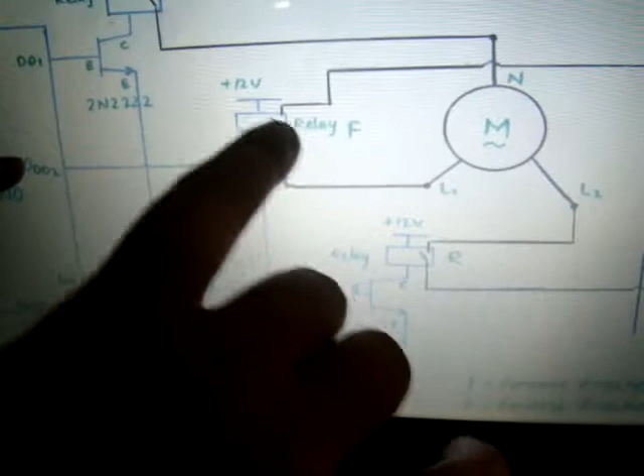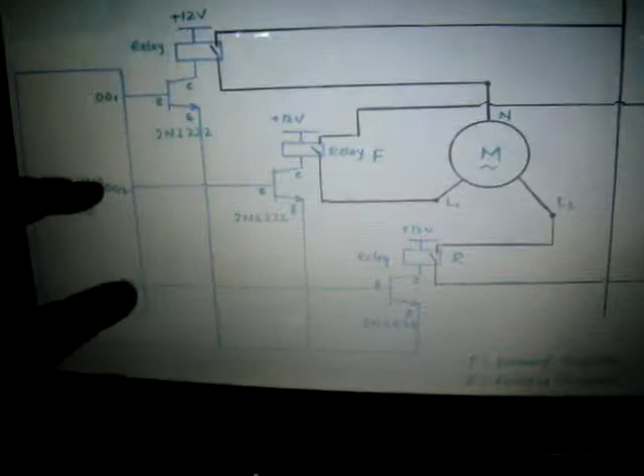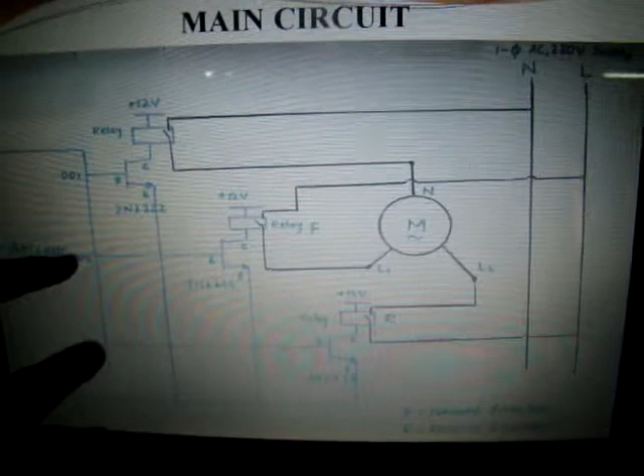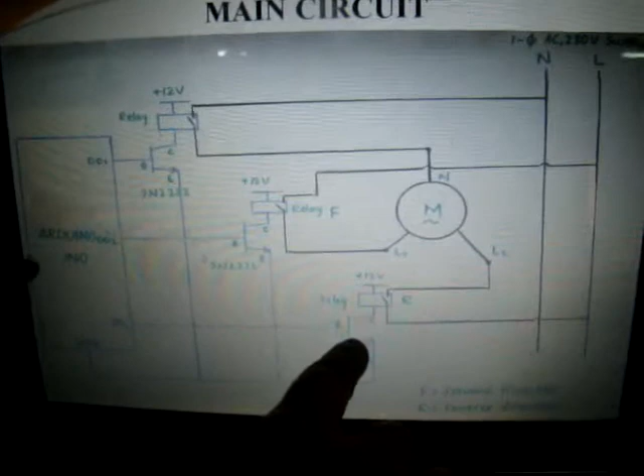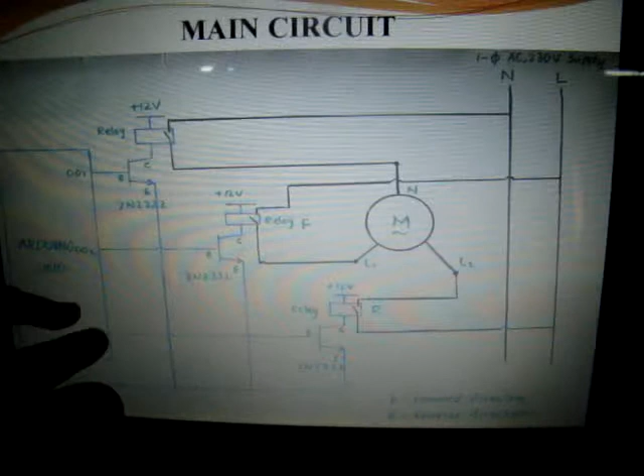The control of the forward and reverse direction of the washing machine can be done by using the relay circuit. For the start of the motor, the neutral of the motor should always be connected to the neutral of the supply. For the forward direction, pin 9 of the Arduino is connected to the transistor and the relay is connected to line 1. To have the forward direction, pin number 10 should always be in low position and pin number 9 should be in high position for the forward rotation of the motor. For the reverse rotation of the motor, pin number 9 should be in low position and pin number 10 should be in high position.